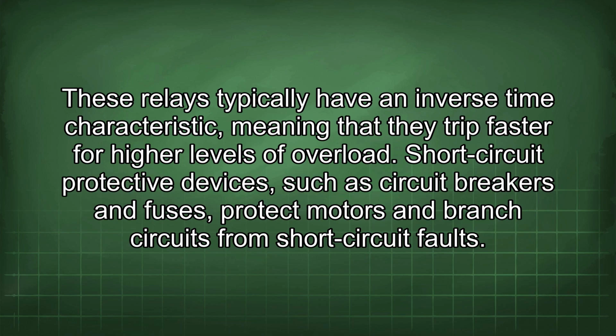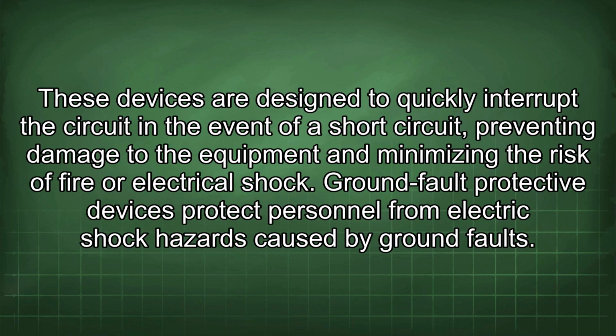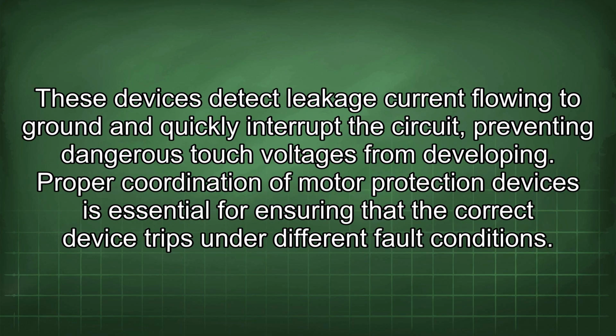Short-circuit protective devices, such as circuit breakers and fuses, protect motors and branch circuits from short-circuit faults. These devices are designed to quickly interrupt the circuit in the event of a short circuit, preventing damage to the equipment and minimizing the risk of fire or electrical shock. Ground fault protective devices protect personnel from electric shock hazards caused by ground faults. These devices detect leakage current flowing to ground and quickly interrupt the circuit, preventing dangerous touch voltages from developing.